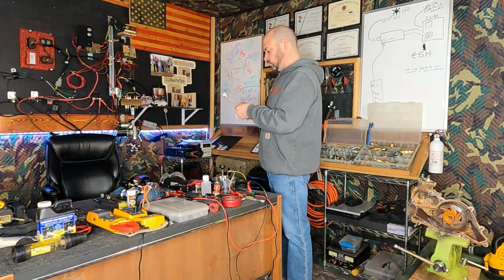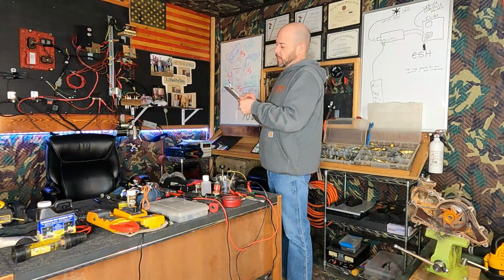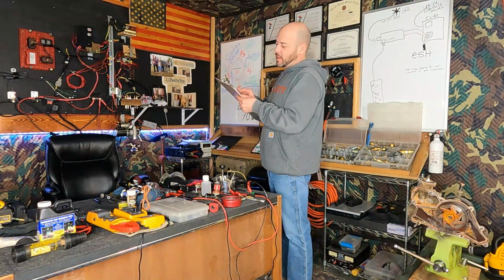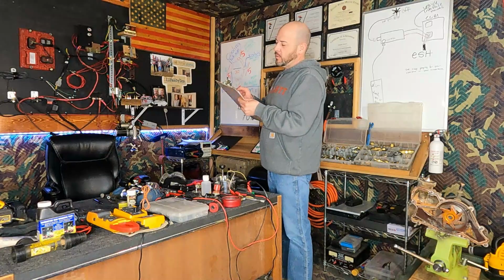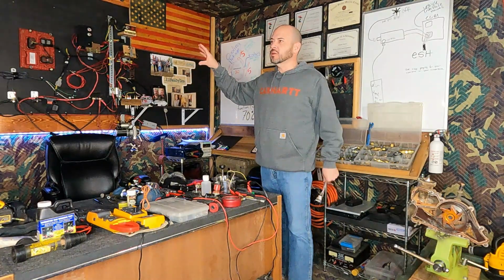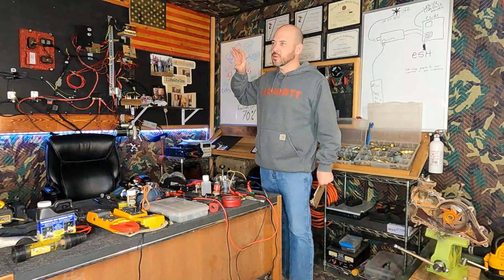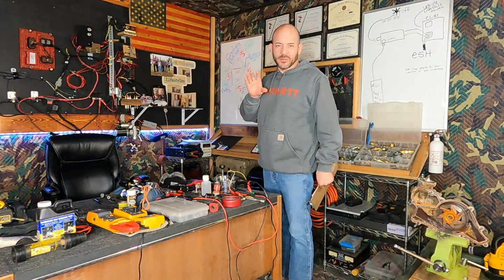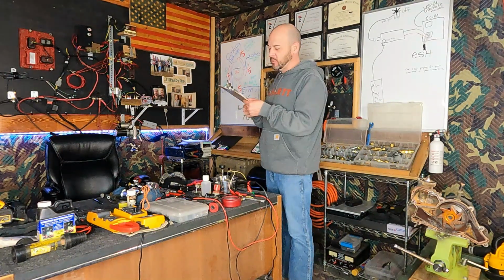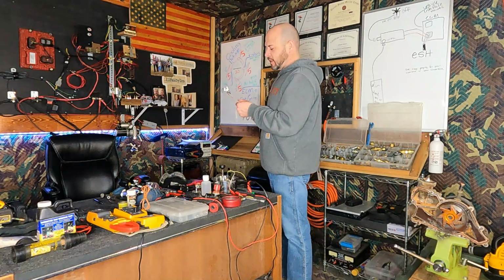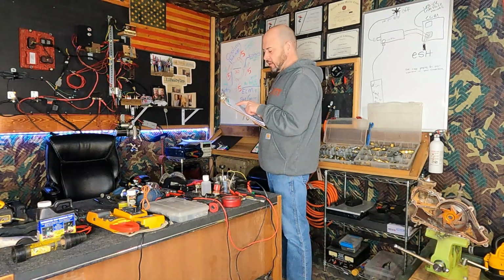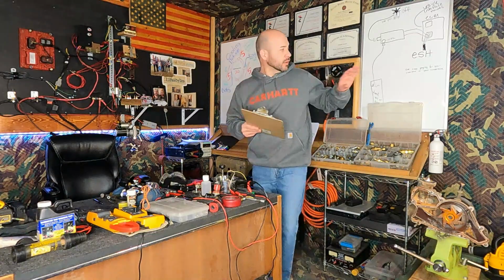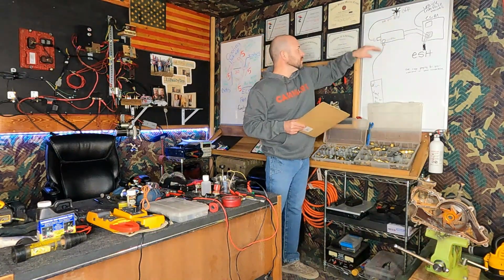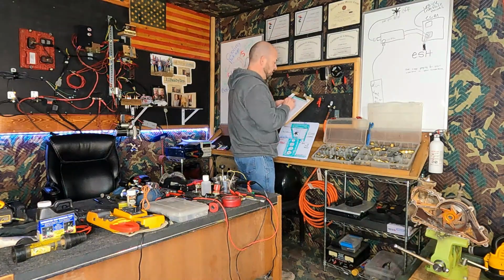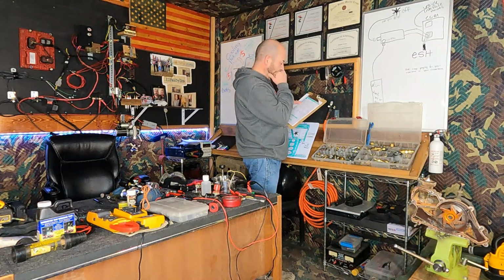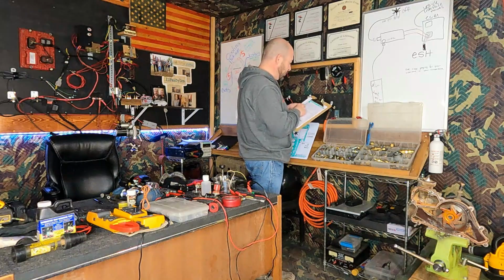So let's talk about the rest of it. This is the interesting part. So coolant mixture, we talked about. Airflow obstruction: a rag thrown in front of a charge air cooler, or cooling package, radiator, condenser, whatever, is not a good airflow test. That is not the way to test them. We'll go over how to do that. So fan slipping, fan solenoid pins, wires, controller, ECM. Remember I talked here about any one of these possible causes of failure, all right? That's just the electrical side of it. So let's look at, well, in a minute I'll go over the air side.